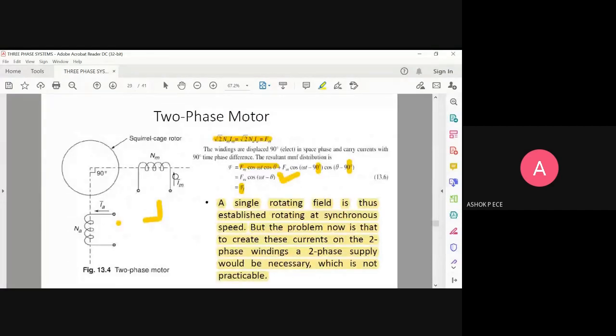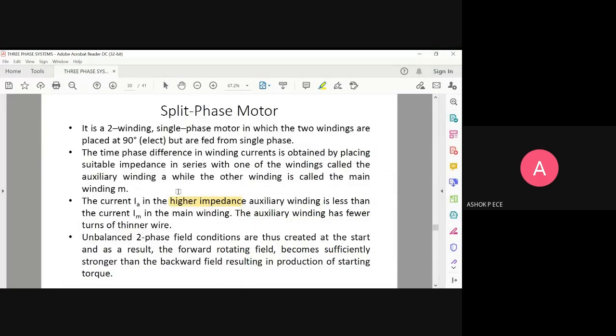IM is your main winding current and IA is your auxiliary winding current. The current in the auxiliary winding is less than that in the main winding. Less current means higher impedance, so the auxiliary winding will have very high impedance and the main winding will have very low impedance.